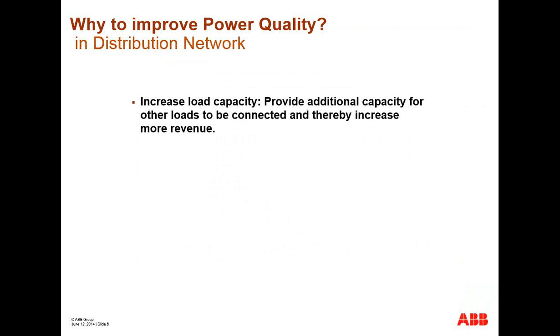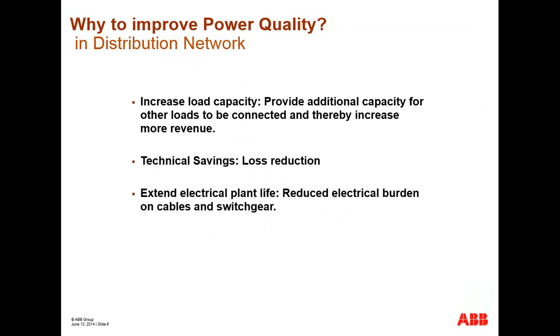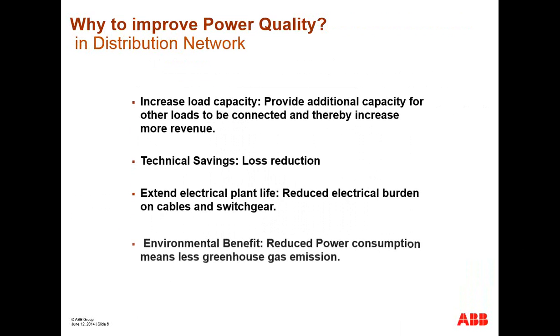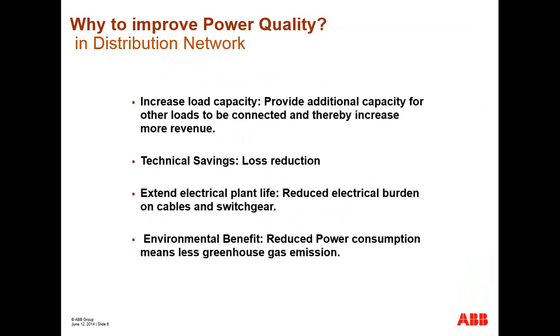If we think about why it is required to improve the power quality, broadly there are basically 4 issues. One is increasing the load capacity, because this provides additional capacity to the distribution system, thereby we will be able to connect more loads and increase the revenue. Technical savings, that is the loss reduction as I explained, which is in the range of 7 to 10% in most of the distribution systems. Extended electrical plant life, which reduces the electrical burden on cables, switchgear, etc. And environmental benefit ultimately, as reduced power consumption means less greenhouse gas emission.